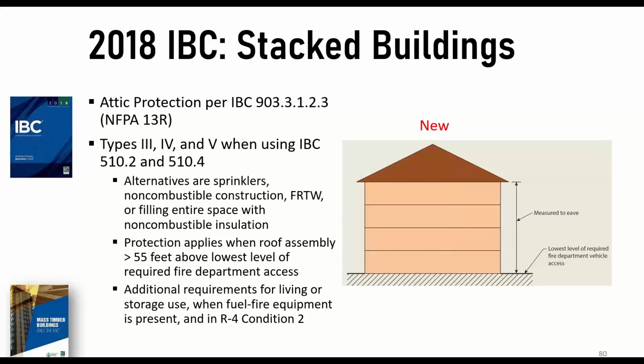There were several notable fires on the East Coast and around the country associated with type 5 buildings with unprotected attics. So the NFPA 13R sprinkler system did not really adequately address the unprotected attic or lofts, unoccupiable loft spaces in some of these larger type 5 buildings. They were typically constructed of materials like light gauge steel and repetitive light wood framing, but they didn't have any provisions for sprinklers in the attic, associated with the lower pressures and lower water volumes of the NFPA 13R sprinkler systems.